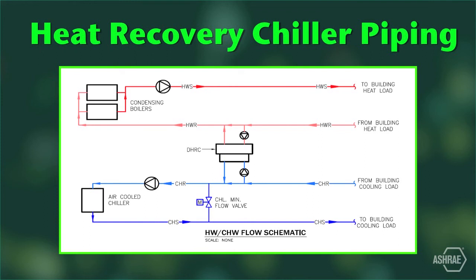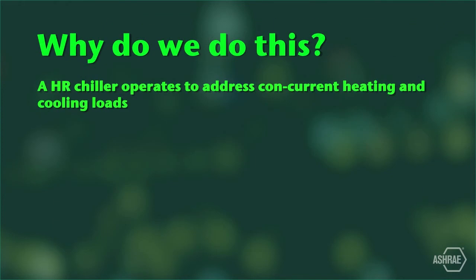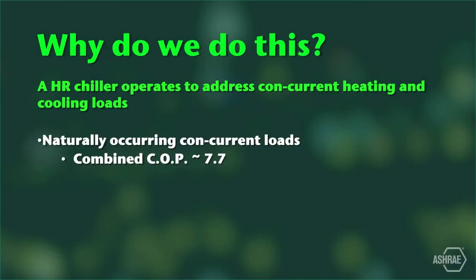The DOAS and the relief air unit piping are similar to a runaround coil, but with the heat recovery chiller, this led to the term enhanced runaround coil. Now, this arrangement does not make any sense without the heat recovery chiller. The heat recovery chiller operates to address concurrent heating and cooling loads. Concurrent loads would typically be summer reheat and winter cooling. Now, when it's very hot outside, the air-cooled main chiller will be operating at about 1.2 kW per ton. The heat recovery chiller will be operating to meet the summer reheat demand, making chilled water at 0.9 kW per ton and getting the reheat for free. That's a combined COP of over 7. And that's what I would call a naturally occurring concurrent load.